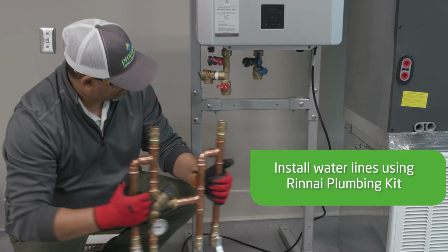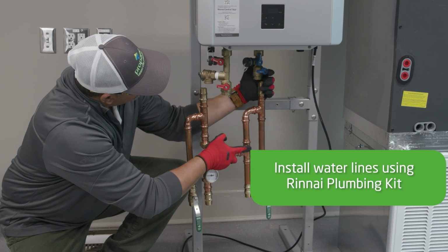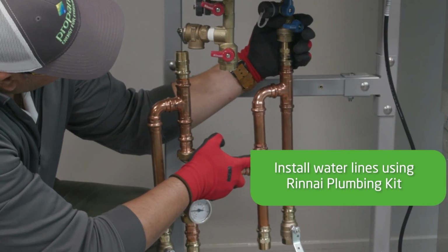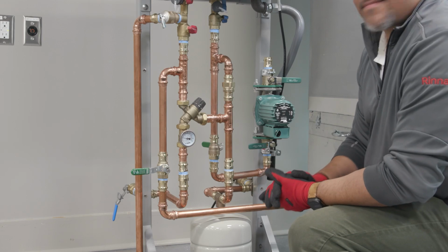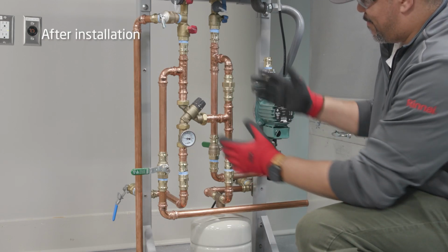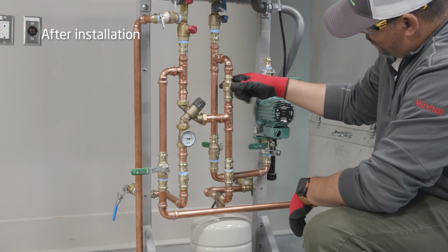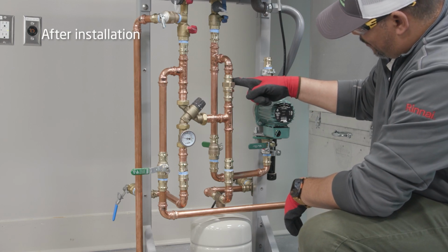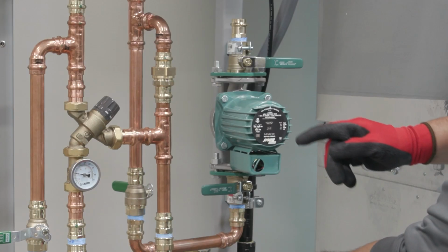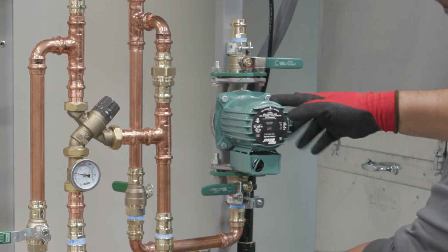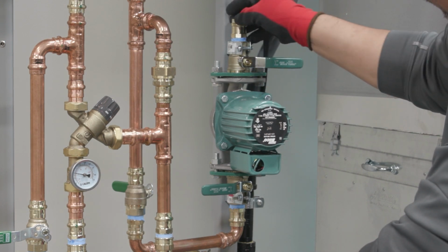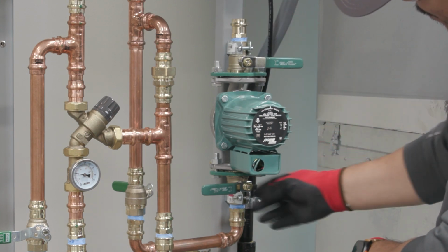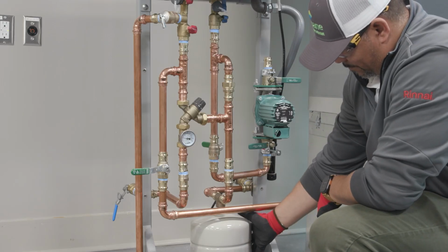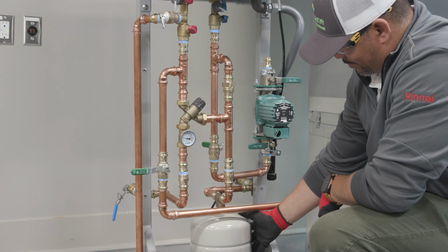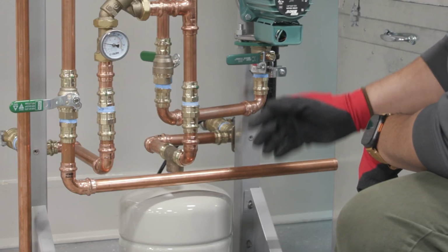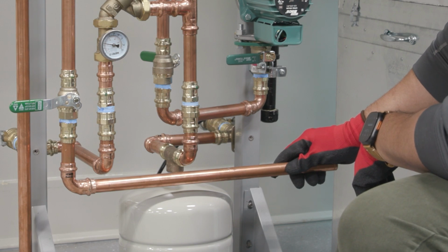Install water lines between the hot water coil and the tankless water heater using the provided Rinnai plumbing kit. We attach the plumbing kit with the help of an additional union, making it easier to connect to the tankless water heater valve kit. Also, you'll see we attach the HPC recirculation pump with the provided flanges and isolation valves. The expansion tank is connected at the bottom to the cold water inlet line. Finally, we've started extending the copper pipe to the hydronic coil and toward the main house.